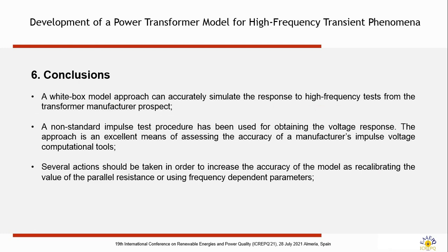Finally, for the conclusions, we have seen that a white-box model approach can accurately simulate the high-frequency transformer response, especially from the transformer manufacturer perspective. We have seen the potential of this non-standard impulse test that has been used for obtaining the voltage response. This approach is very useful for calibrating the simulations and transformer model tools.